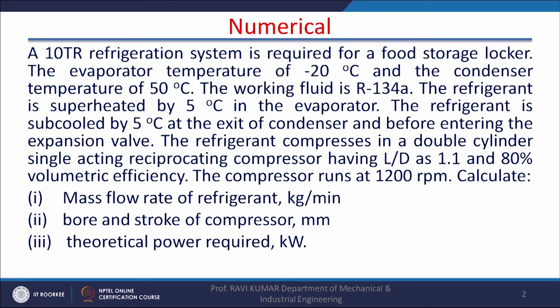A 10 TR refrigeration system is required for a food storage locker. The evaporator temperature is minus 20 degree centigrade and the condenser temperature is 50 degree centigrade. The working fluid is R134A. The refrigerant is superheated by 5 degree centigrade at the exit of the evaporator, and sub-cooled by 5 degree centigrade at the exit of the condenser before entering the expansion valve. The refrigerant is compressed in a double cylinder single acting reciprocating compressor having L by D as 1.1, with 80 percent volumetric efficiency. The compressor runs at 1200 rpm. Calculate: mass flow rate of refrigerant in kg per minute, bore and stroke of compressor in millimeters, and theoretical power required in kilowatts.